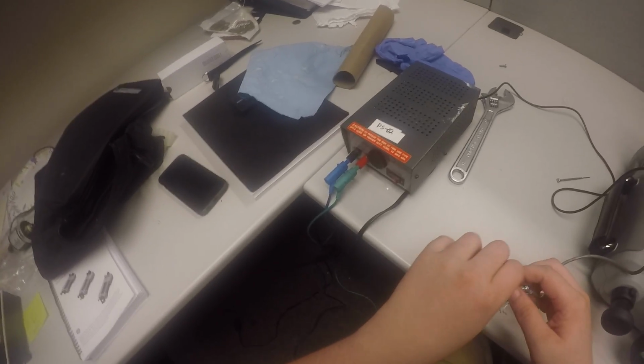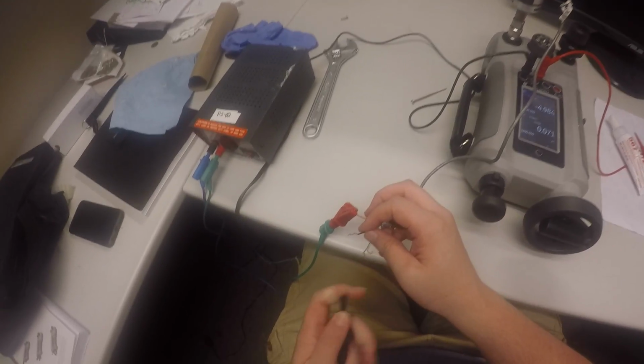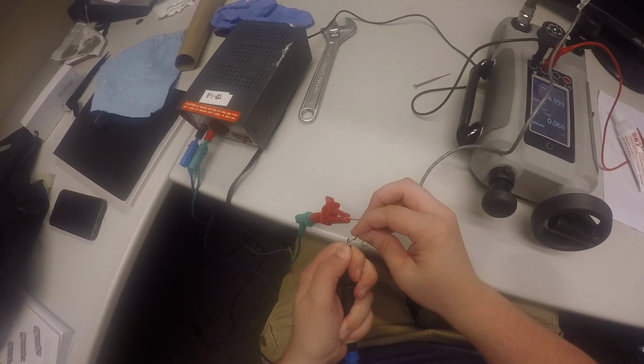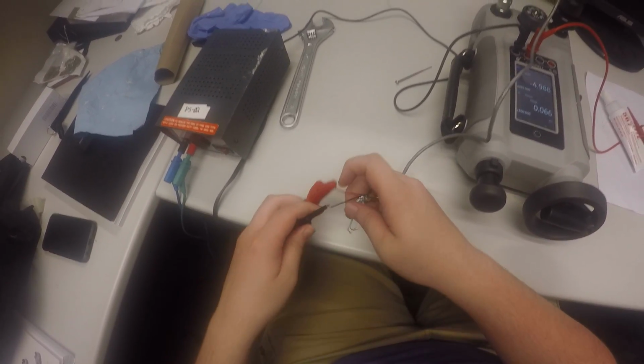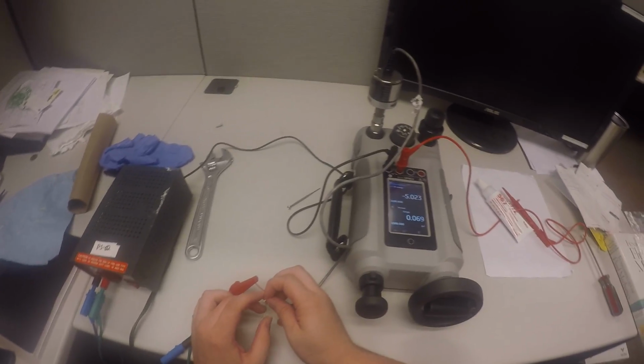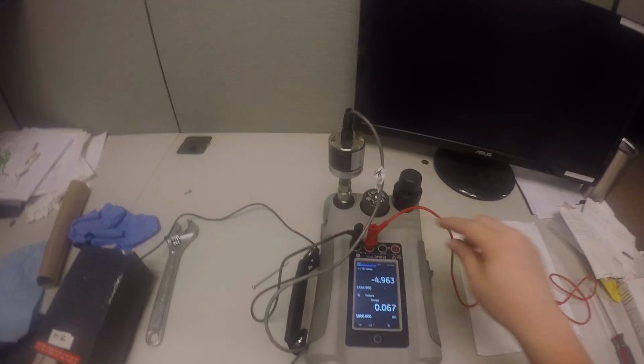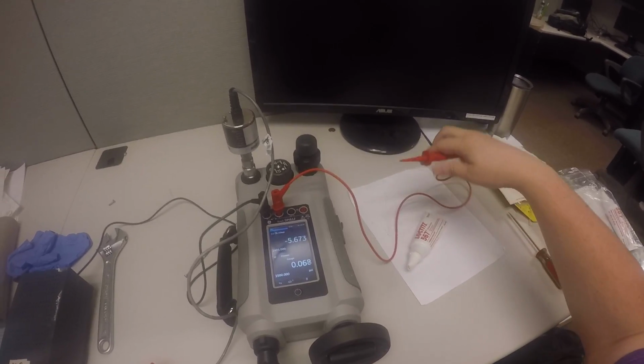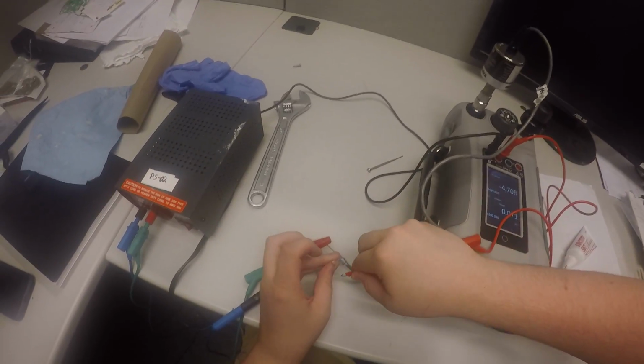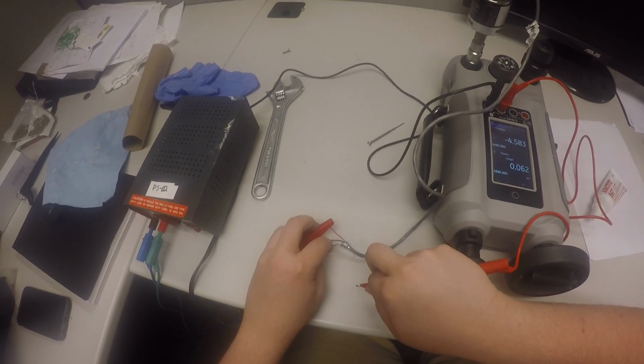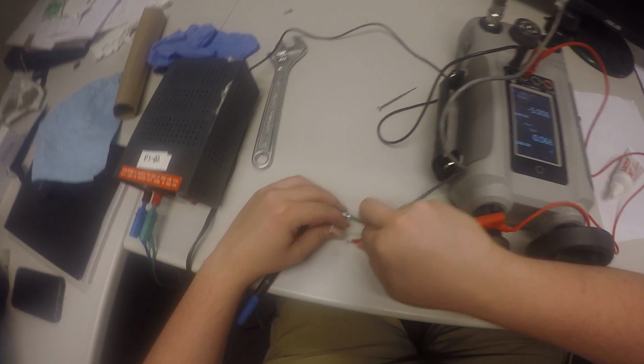So that's hooked up. Now the negative part is the black wire on this one. Alright. Okay, now the output from the transducer goes directly into the Druck, as seen here. And the red is the positive input into the Druck, or output from the transducer. So we're going to hook that up to the green wire in this case for this one. And the negative output of the transducer is this white wire. So we're going to plug that into the black part on the Druck.